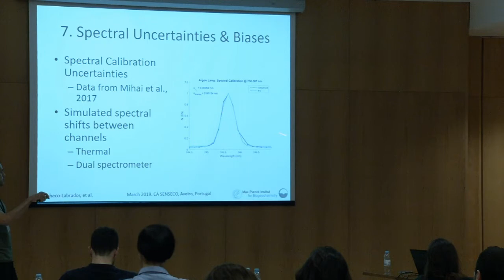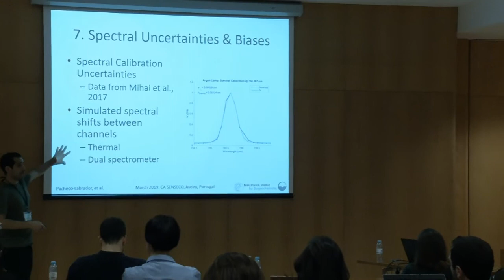The story changes a lot if the shifts are from one channel with respect to the other. Then, of course, the residual of fluorescence is really sensitive to this, and the noises are above the level of the signal actually, and it's totally worthless. So this is a very strong message. Never measure fluorescence with two different spectrometers. If this is a system you are trying to develop, save money by using only one spectrometer, because you will never manage to match the two things.